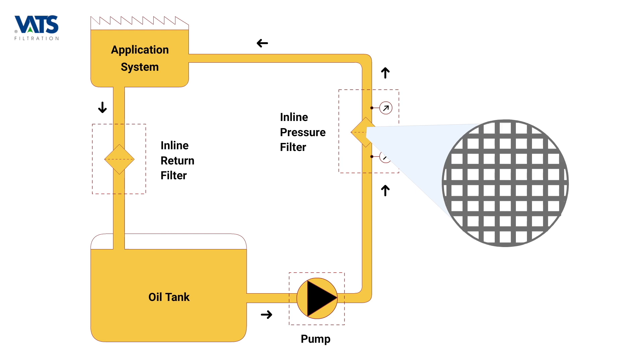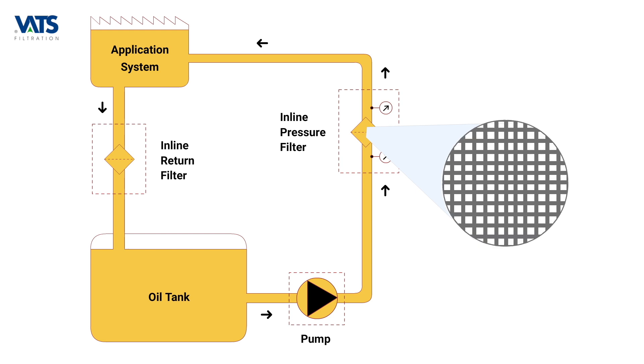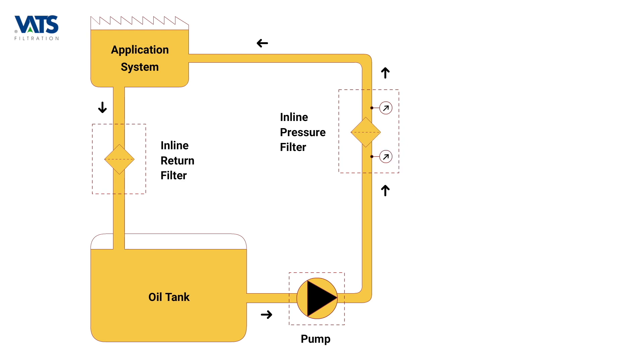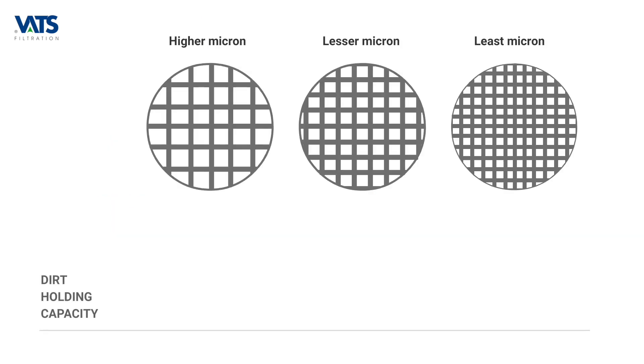Most inline pressure filters for hydraulic or lubricating systems are of this type, and the micron size is decided based on the tolerances of mainly the servo control valves and other critical components of the system. They work very well for the purpose of safeguarding the system, but going down in micron size reduces the dirt holding capacity, causing the filter to clog and need replacement more frequently — and this is expensive.